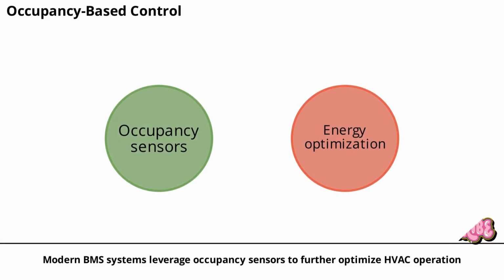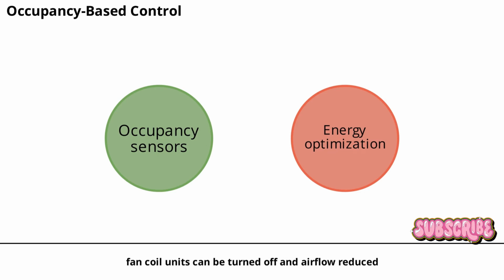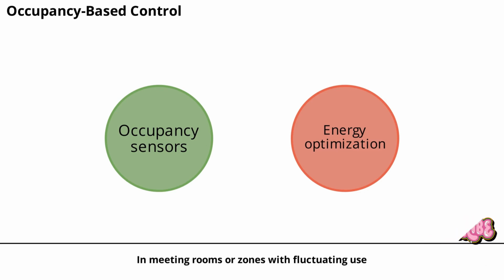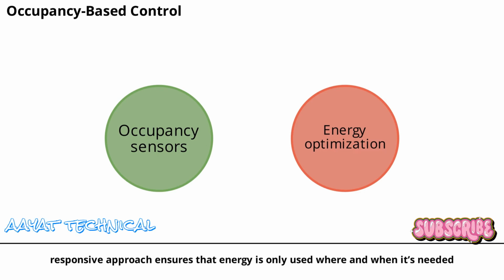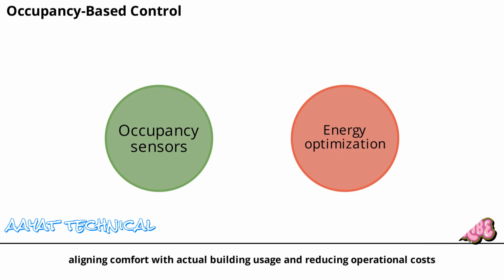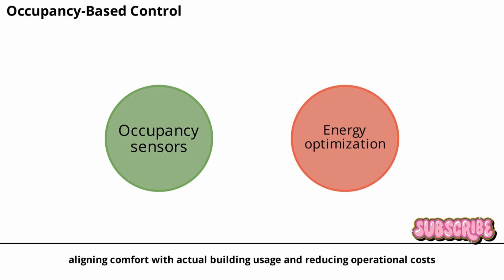Modern BMS systems leverage occupancy sensors to further optimize HVAC operation. When a space is unoccupied, fan coil units can be turned off and airflow reduced, saving energy. In meeting rooms or zones with fluctuating use, the system adjusts conditions in real time. This smart, responsive approach ensures that energy is only used where and when it's needed, aligning comfort with actual building usage and reducing operational costs.